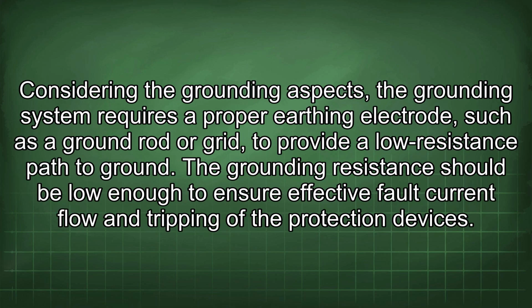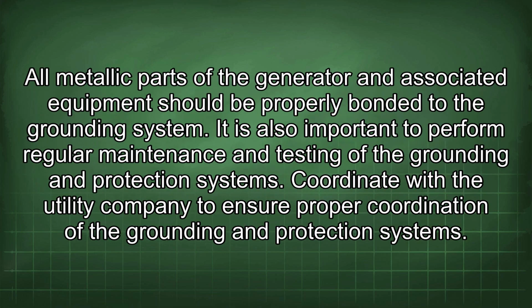Considering the grounding aspects, the grounding system requires a proper earthing electrode, such as a ground rod or grid, to provide a low resistance path to ground. The grounding resistance should be low enough to ensure effective fault current flow and tripping of the protection devices. All metallic parts of the generator and associated equipment should be properly bonded to the grounding system. It is also important to perform regular maintenance and testing of the grounding and protection systems.